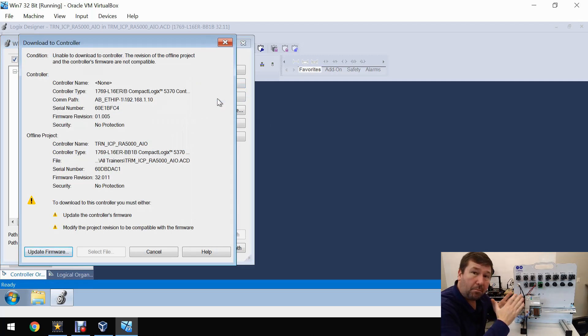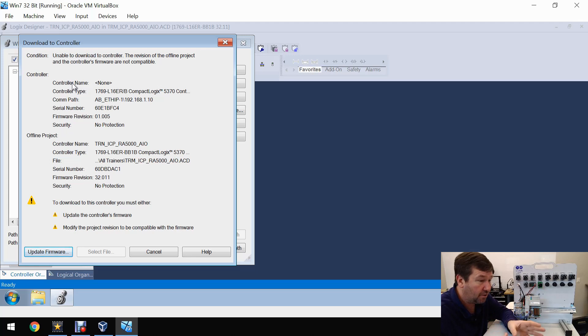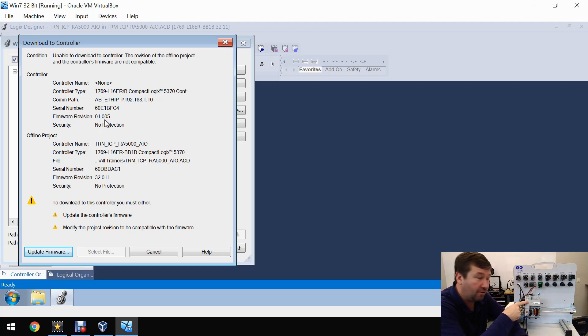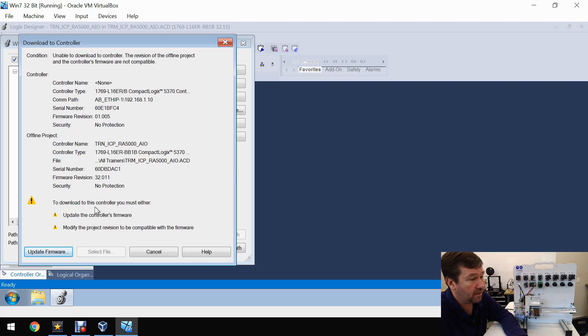Since this is a brand new PLC out of the box, we're going to see a dialog that says the firmware in our Studio 5000 program doesn't match the firmware of this PLC. The controller firmware — what's in here — is version 1.005, which is pretty much what they are brand new out of the box, and we're running version 32 over here. So first we're going to need to update our firmware.